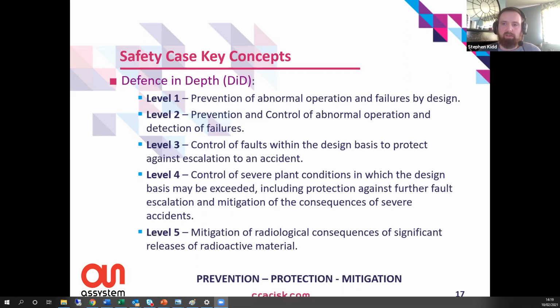Level four is about severe accidents. These are scenarios to account for particular severe challenges, such as extended loss of off-site power combined with common cause failure of diesel generators. These are extreme scenarios that are looked at, also to account for potential errors in the analysis supporting the level three measures.